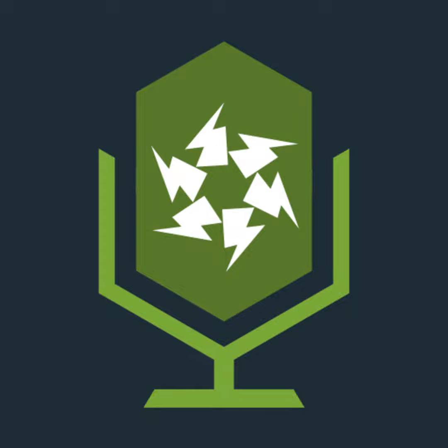When I look at table 41.2 and table 41.4, if I keep flicking between them, they both have the same fuses in them. They're both BS 88.2s, they're both BS 88.3s, and they're both 3036s. But I'll notice that the actual fuses in one of them only go up to 63, whilst the other one goes all the way up to over 100.